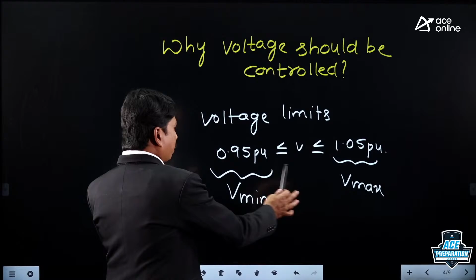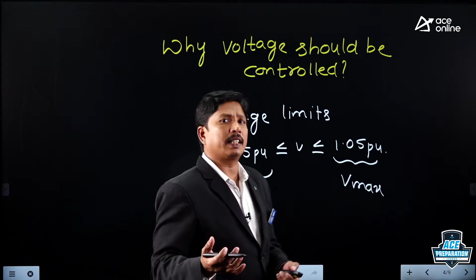Now we are saying that the voltage should be between minimum and maximum. The maximum we are specifying because of the insulation problem. What is the reason for specifying a minimum voltage? Why are we specifying the minimum voltage in the system? Have you seen any incandescent bulb in your homes? It glows dim sometimes, and the TV screen starts rolling from top to bottom sometimes, and the ceiling fan is unable to rotate at the rated speed, or even though the regulator is at 5, the fan rotates very slowly. We can say the reasons for these are the low voltages.